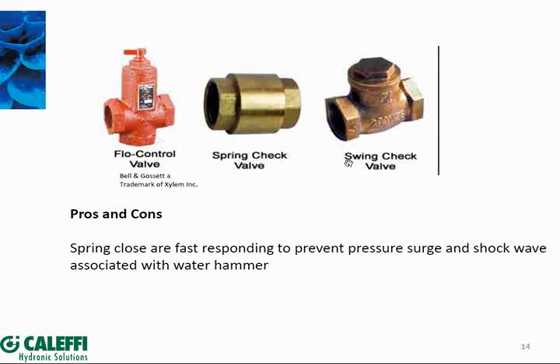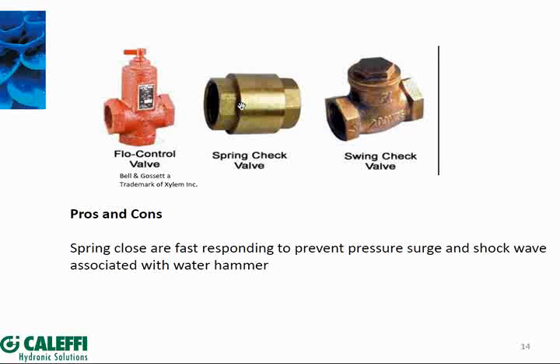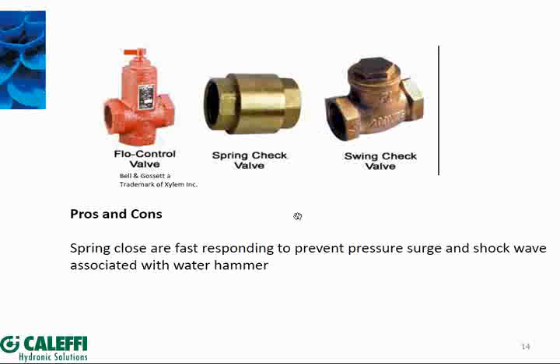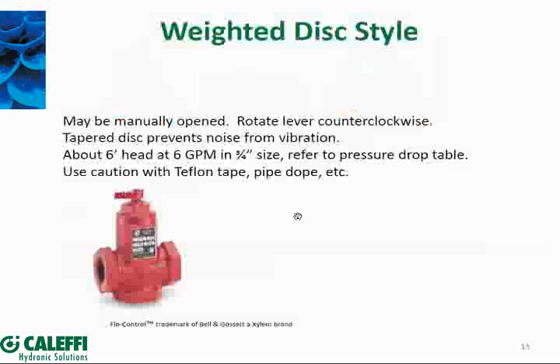Now let's talk about swing checks. This cutaway example is actually a pretty good one — most inexpensive ones don't have the notch that allows the gate to swing 100% out of the way. The difference between a wide pattern and a straight pattern swing check is how far the gate can swing open. A couple things with this type of valve: it has a very high CV because when the gate swings completely clear, you have full port flow. However, it's also soft-seated, so these can get a bang or hammer when they close.